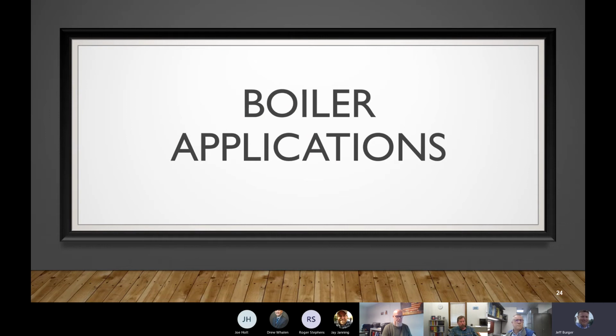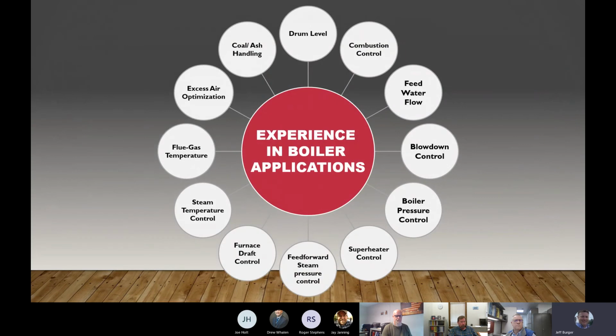We'll dive into a couple of different applications here. One is a boiler application. The HC900 really fits well into package boilers and large utility boilers, and it offers process control for many different areas in the boiler and around the boiler. As you step through these: coal and ash handling, drum level, obviously combustion control, feed water flow, blow down control, boiler pressure control, superheater control, feed forward steam pressure control, furnace draft, steam temperature control, flue gas, and last but not least, the excess air. All of these applications require pretty intense process control along with discrete control, and the HC900 really performs well in these types of applications.